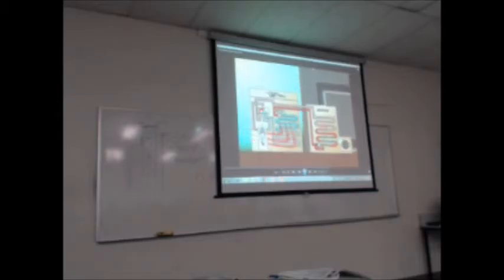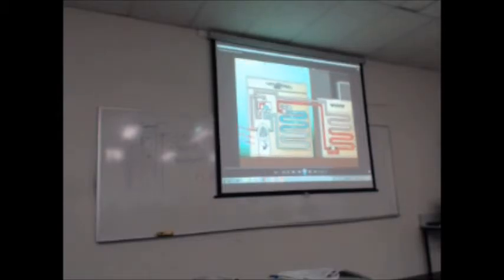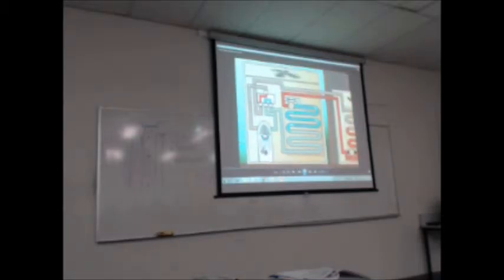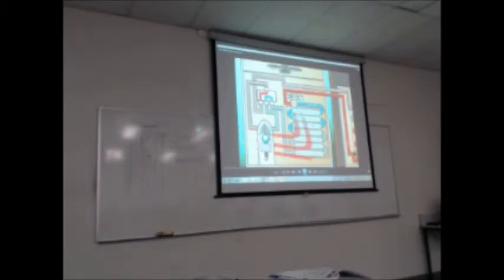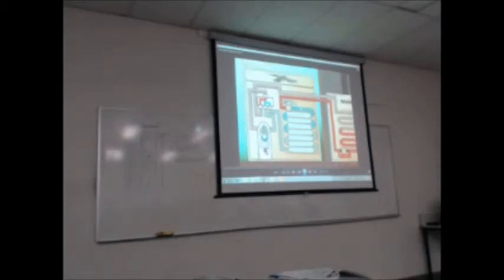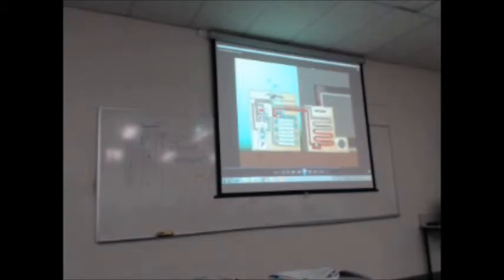This is a very efficient and cost-effective method for heating the home. There is one inherent problem, however. In order for the evaporator, now outside, to absorb heat, it must operate at temperatures lower than the outside air. This very low operating temperature allows ice or frost to accumulate on the outside of the evaporator. The remedy, the defrost cycle.